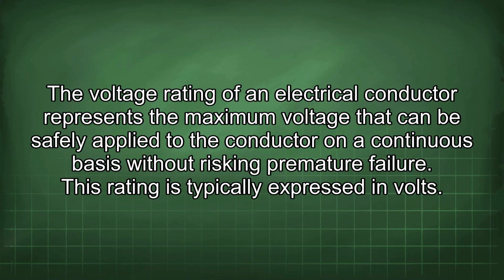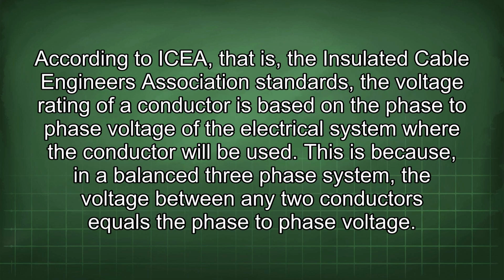The voltage rating of an electrical conductor represents the maximum voltage that can be safely applied to the conductor on a continuous basis without risking premature failure. This rating is typically expressed in volts. According to ICEA, that is, the Insulated Cable Engineers Association standards, a voltage rating of a conductor is based on the phase-to-phase voltage of the electrical system where the conductor will be used. This is because, in a balanced three-phase system, the voltage between any two conductors equals the phase-to-phase voltage.